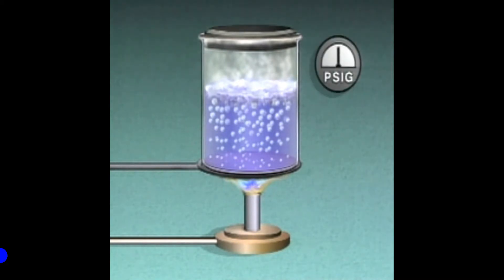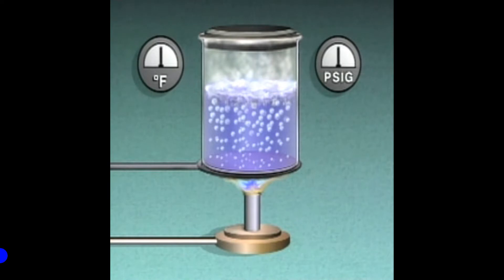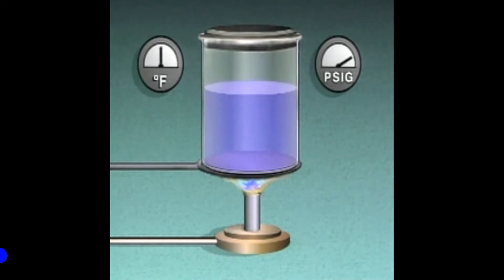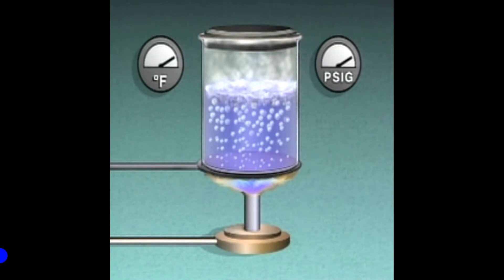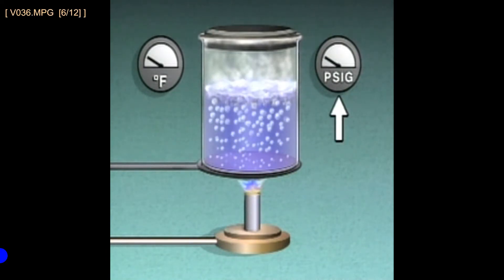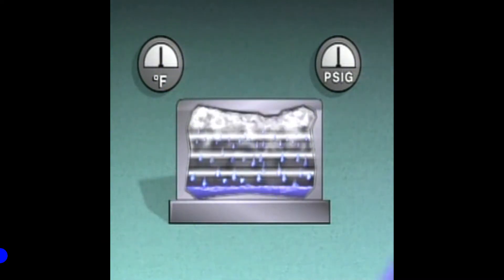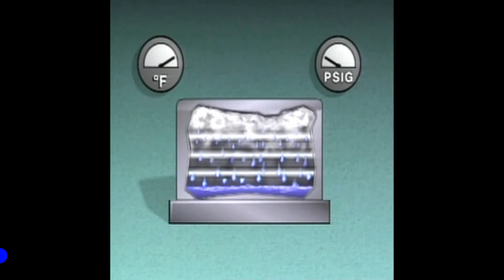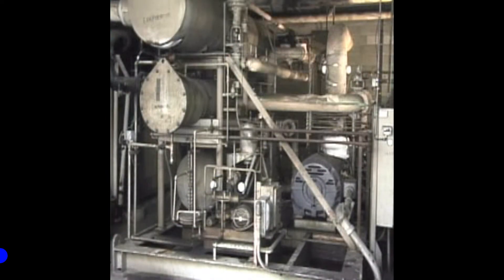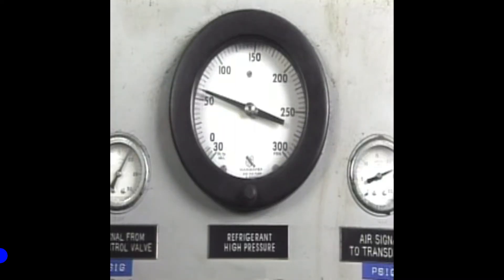When the water in this beaker is at atmospheric pressure, it boils at 212 degrees Fahrenheit. If the pressure on the water is increased, the water no longer boils at 212 degrees — more heat is needed to reach the new higher boiling temperature. If the pressure on the water is reduced, the water starts to boil at a temperature lower than 212 degrees Fahrenheit. Pressure has a similar effect on condensing temperature: when the pressure is increased, steam condenses at a higher temperature, and when the pressure is decreased, steam condenses at a lower temperature. The same effect occurs with the refrigerants in refrigeration systems — when the refrigerant is at a higher pressure, it boils or condenses at a higher temperature.